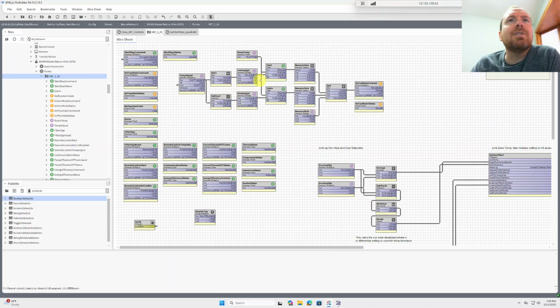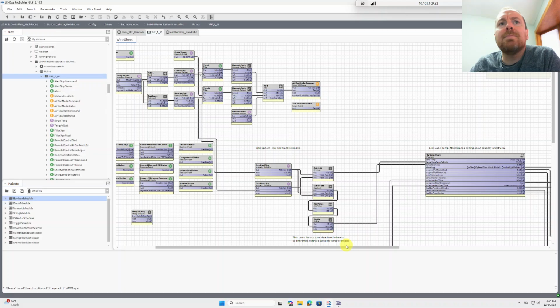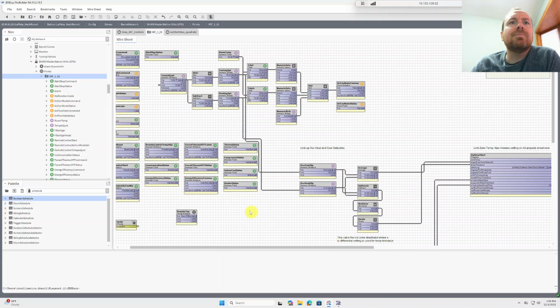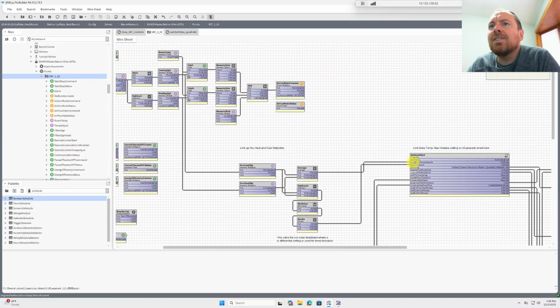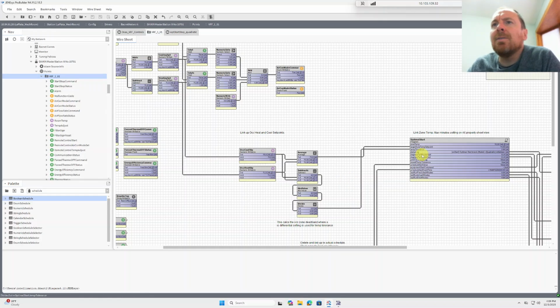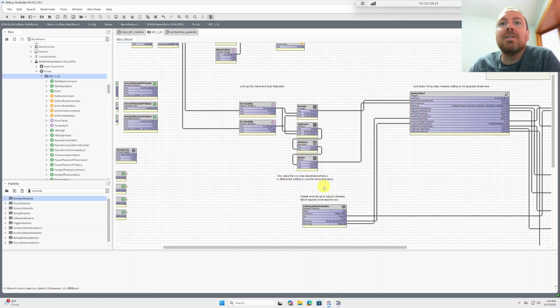So I am just going to grab this cooling, feed it into mine, grab the heating, feed that into mine. Maybe I'll move some of their points out of the way, clean it up a little bit. That's actually calculating this target zone set point, and the temp tolerance of 2 degrees.